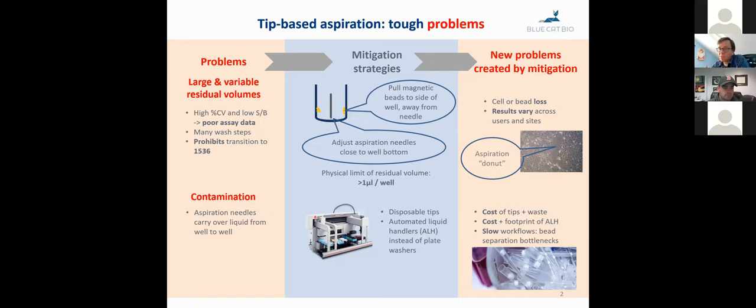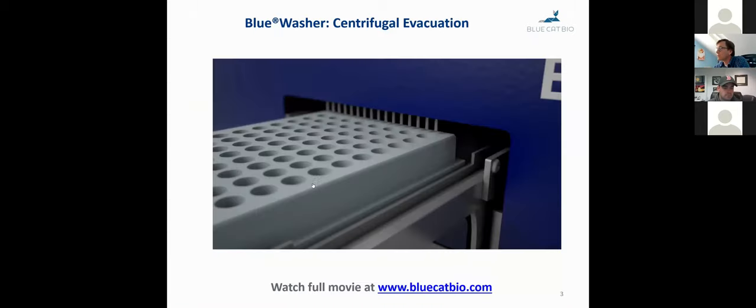In terms of contamination, since needles, when you use the same one for different wells, carry tiny amounts of liquid over, they're not suitable for NGS-type workflows. So the mitigation strategy is to use disposable tips and automated liquid handler, which in turn causes problems on the financial side, because the cost of disposable tips adds up. You also generate a lot of waste. Then there's the cost and the footprint of the liquid handlers. And then the magnetic bead separation steps really slow down workflows if you do a tip-by-tip.